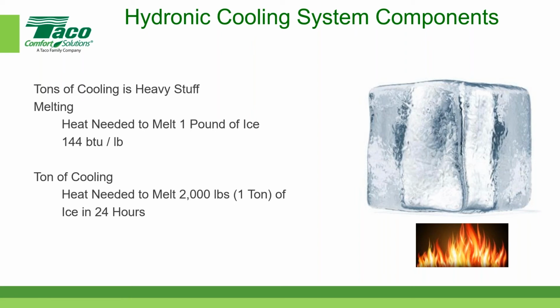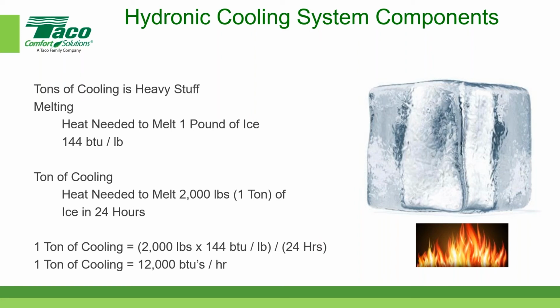So if we add heat to a block of ice that weighs a ton, and we add that heat over a 24-hour period to melt all of that ice, it comes out to 1 ton of cooling is equal to 2,000 pounds times 144 BTU per pound divided by 24 hours. Comes back to that same magic number that we had before, which is 12,000 BTUs per hour. And again, HR is hour, not human resources.